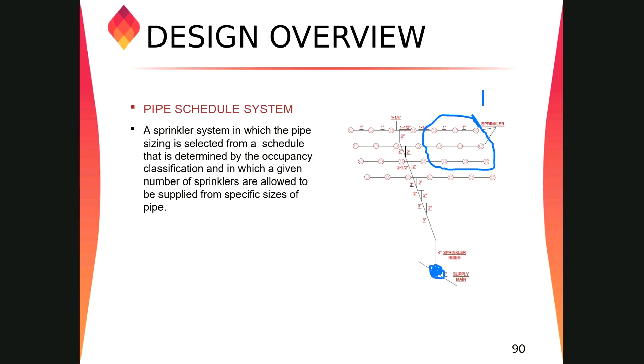But when performing those calculations on the pipeline, they never worry about the nodes. They just worry about which is the most distant or remote location, and they perform the calculation. In Elite, yes, we have to come from the remote location by keeping node 1 here, node 2, node 3, node 4, 5, 6, 7, 8, 9, and then 10 to 16. This is the way we have to put the nodes into our software for doing the calculation.